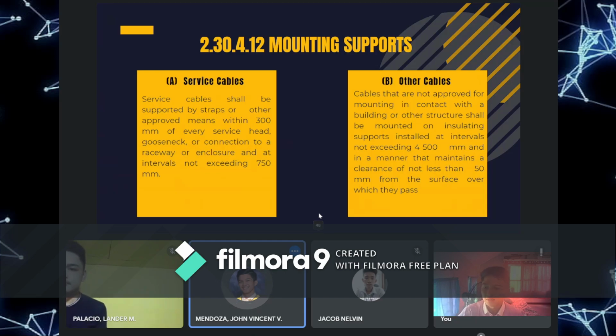So para naman dito, dapat natin gamitan ng insulator yung cables para makabit natin sa mga buildings or wall. Bawal ito sumagi sa wall dahil magko-cause ito ng ground pag nagkiskisan yung wall and yung wire. Pwedeng mabalatan yung wire natin pag nagkiskisan sila sa wall. So ang dapat yung allowance between the wall and the wire is dapat hindi bababa ng 50 millimeter. And yung sa interval naman between support, hindi siya tataas ng 4,500 millimeter dahil kung lumagpas tayo dito, pwede itong mag-cause ng pagsayaw ng cable natin caused by wind current. Ito yung sinasabi ko kanina, kagaya din sa service cables.